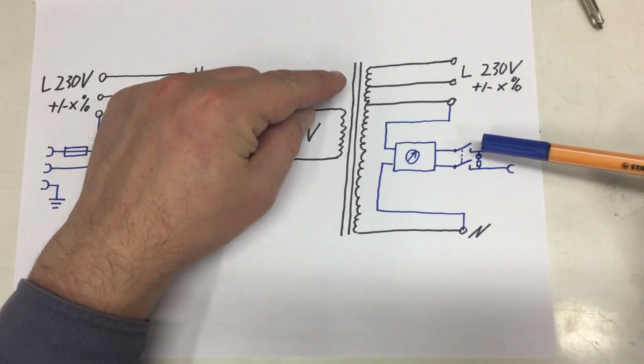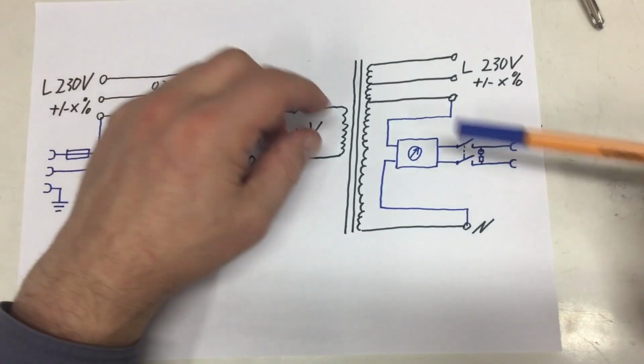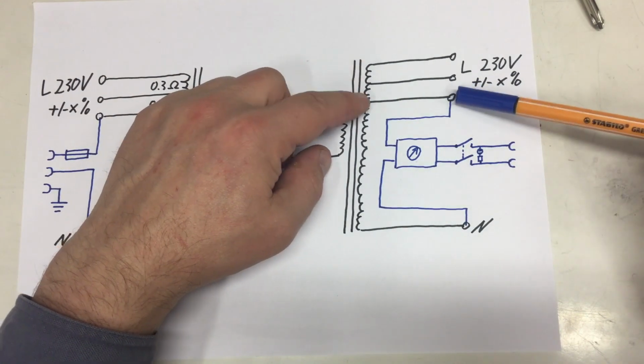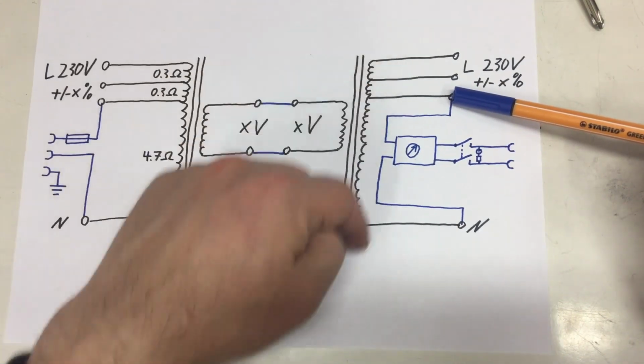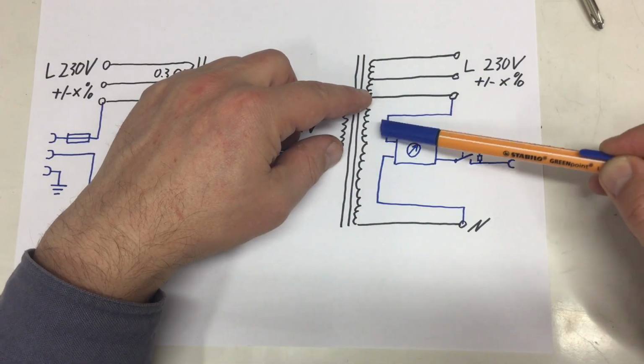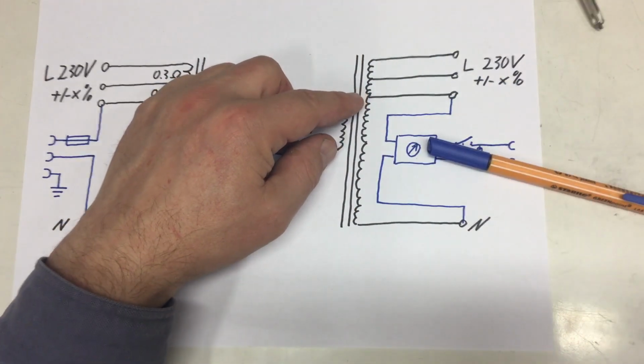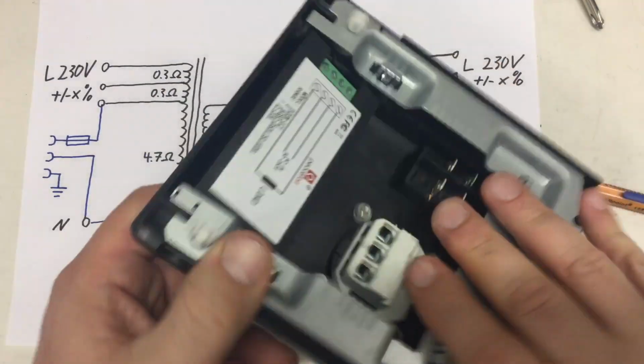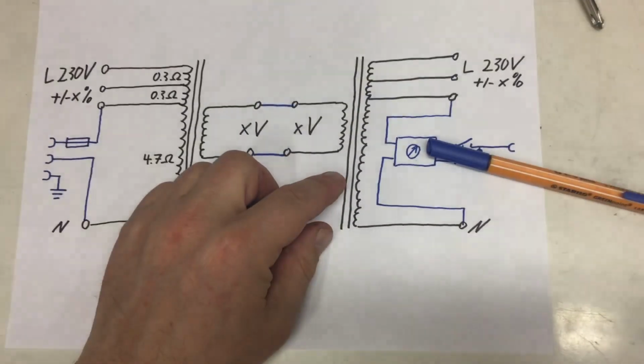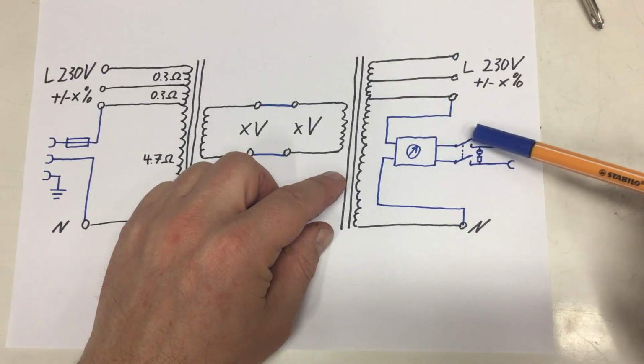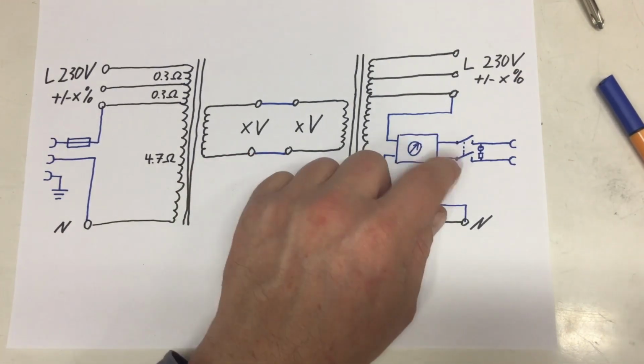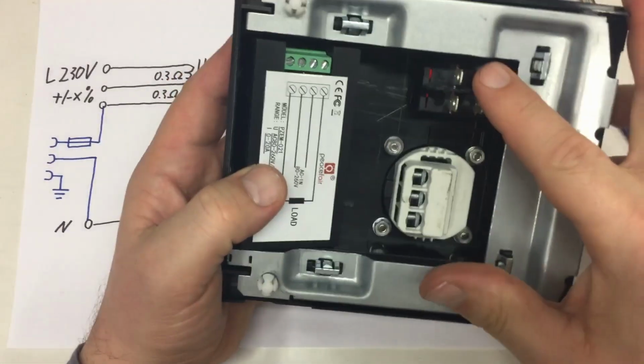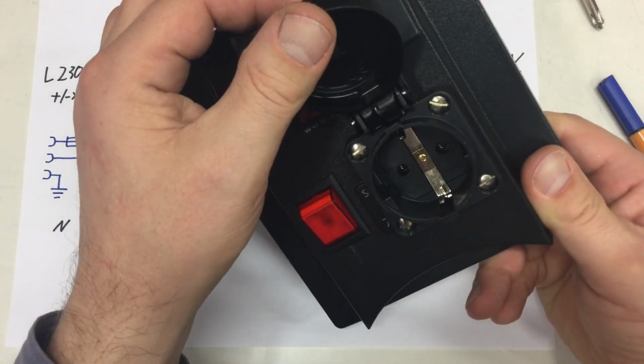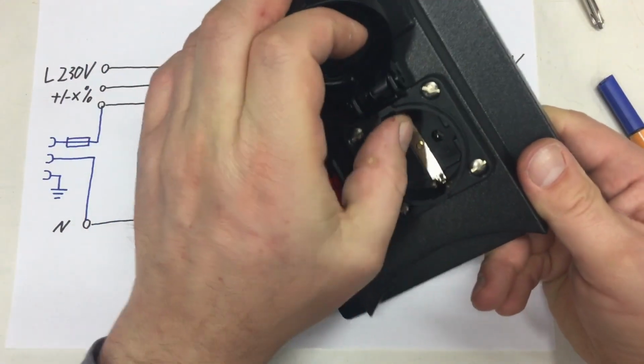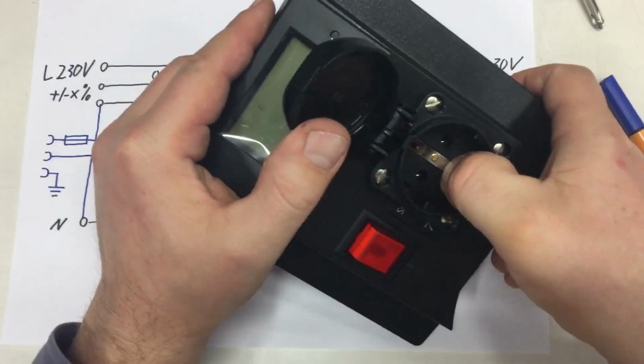And then on the isolated side, we take neutral and the lowest tap of the high side of the transformer. We go into the meter. And then we go into that switch, yeah, both lines. And then we go into the output socket, only 2 poles. The earth connections will not be wired.